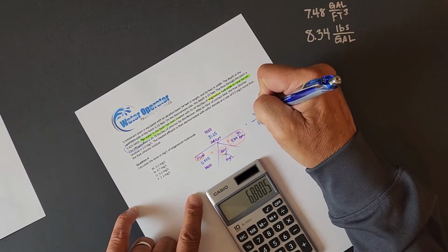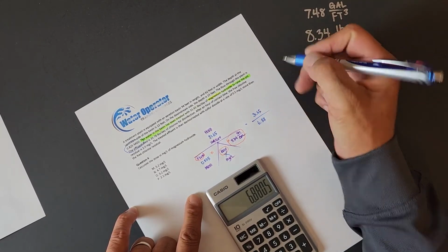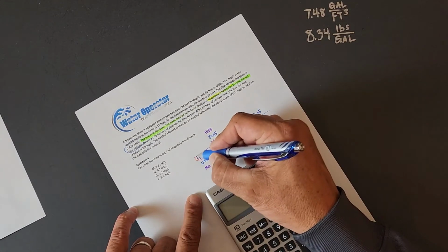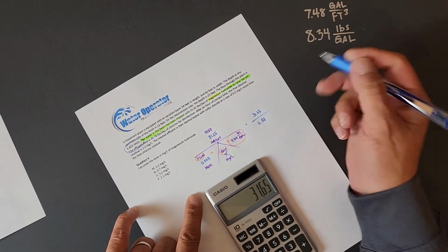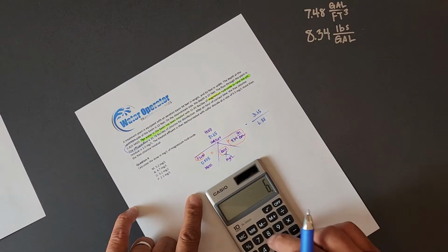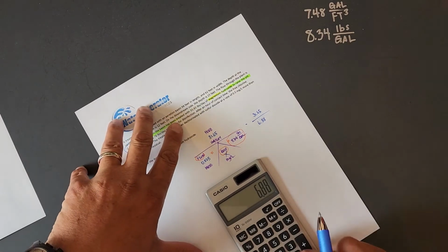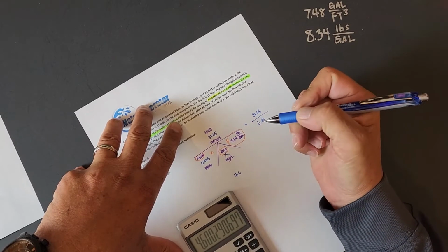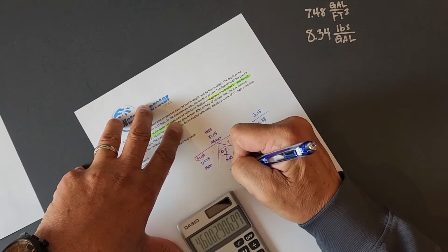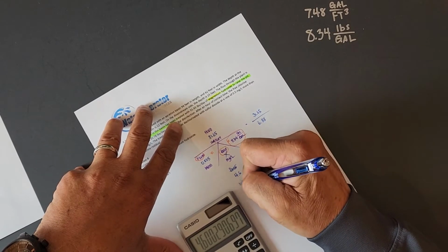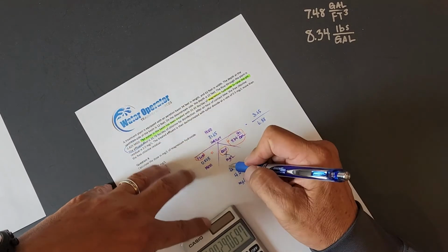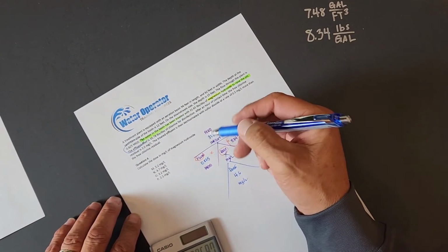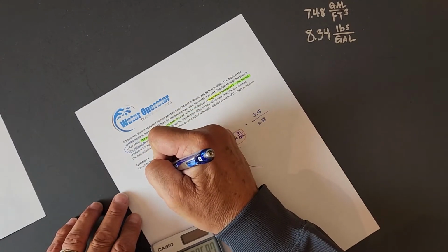Our feed, 31.65 pounds per day. So let's take that 31.65, and this line right here represents division. This is our division line. Divide that by 6.88, and we get 4.6. Our dose is 4.66 milligrams per liter. That is our piece of the pie. The best answer, 4.7.